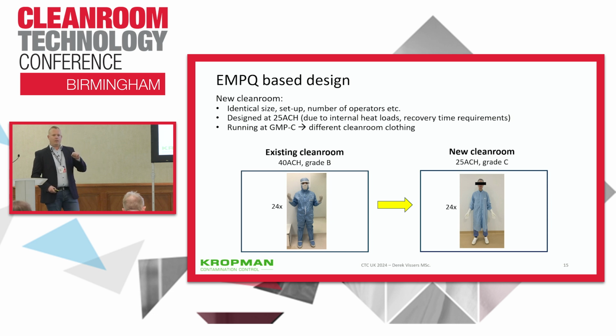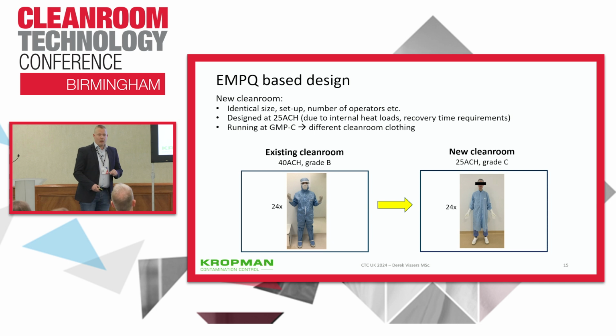Later on, the same client asked us to build a new clean room in the same facility. Identical size, identical setup, identical number of 24 operators. We decided to design it at 25 air changes and not 40 due to expected internal heat loads and also because of recovery time requirements. Later on, the client decided to run it at GMP C and not at level B. So the main difference is gowning. In grade B the face is fully covered, and in grade C the face is not covered at all.